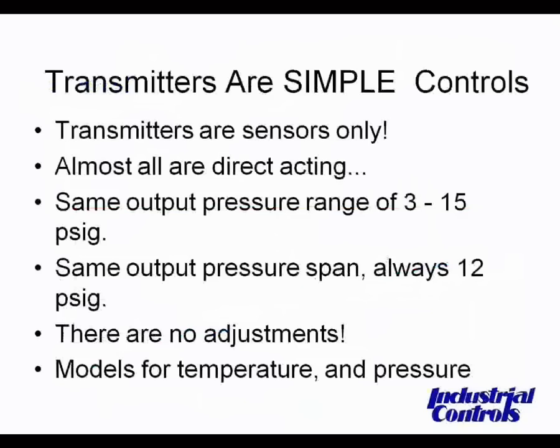Let's reiterate a couple of points on the transmitters. Transmitters are sensors only. Almost all of them are direct acting. All have the same output range of 3 to 15 PSIG. Same output span, always 12 PSIG. There are no adjustments — you cannot adjust these in the field. Models are available for temperature, pressure, and humidity.